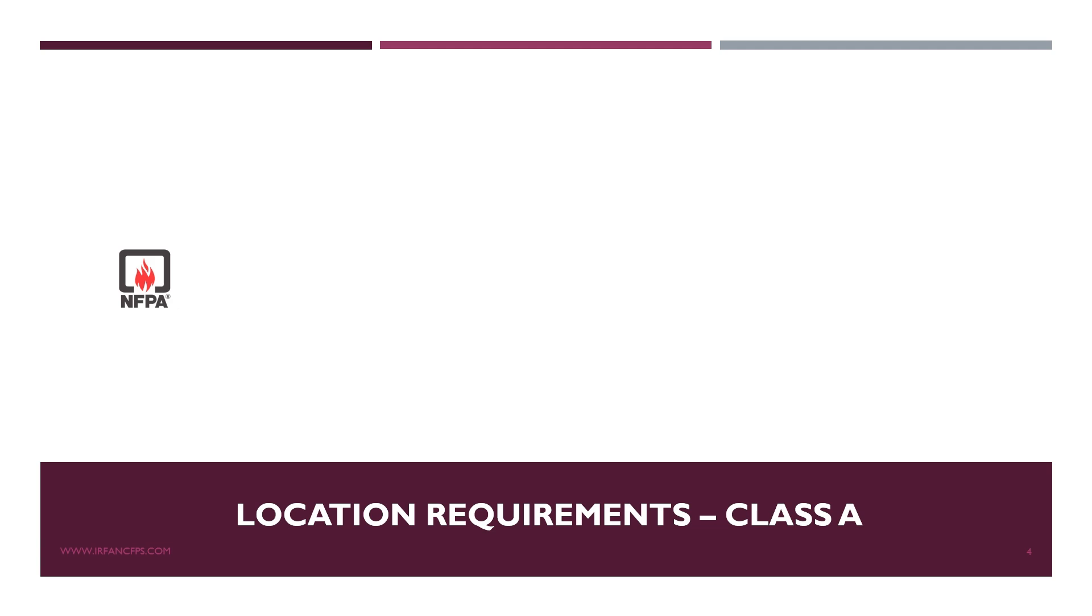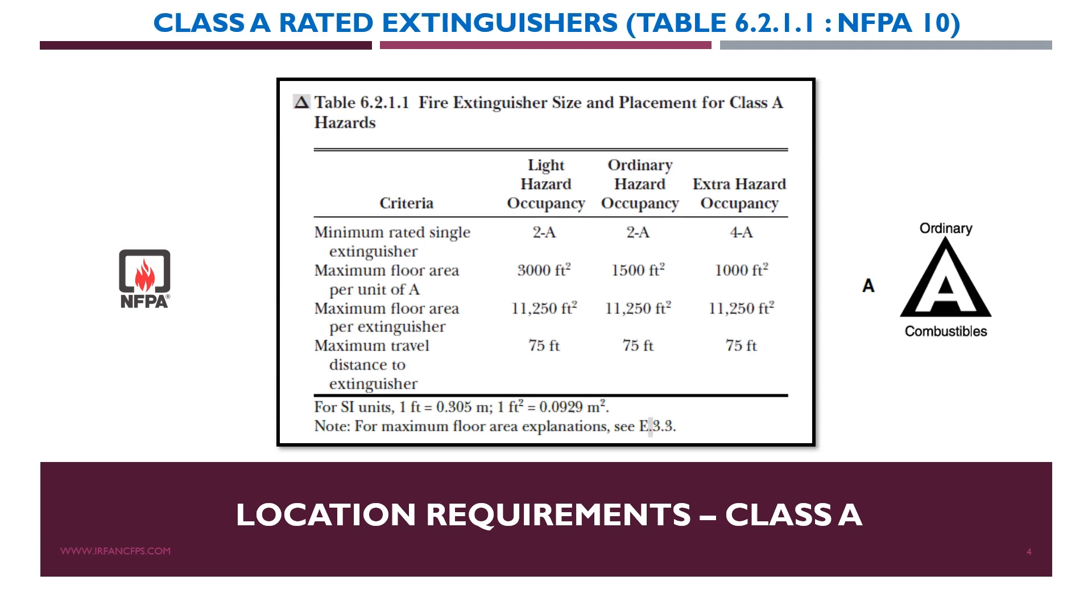So I have extracted a table from NFPA 10 which is referring to the class A hazards. So basically we will discuss about the upper portion later on. But for now just remember the maximum travel distance to fire extinguishers shall not be more than 75 feet or 22.9 meters for any hazard occupancy. See the definition of light hazard occupancy, ordinary hazard occupancy and extra hazard occupancy for extinguishers is different than the occupancies which we have defined in sprinkler system.